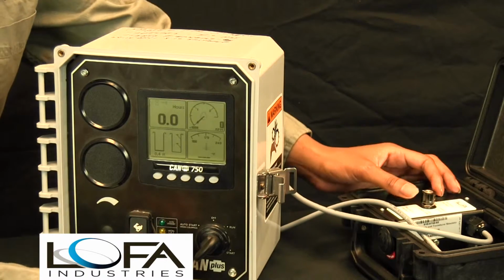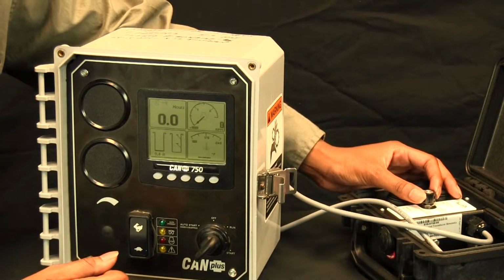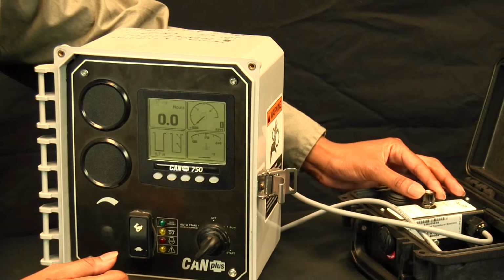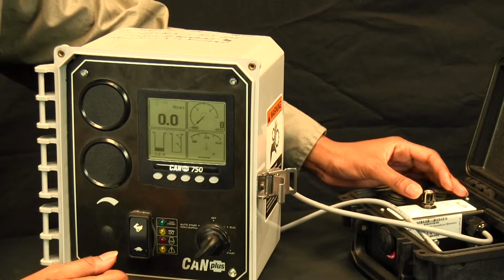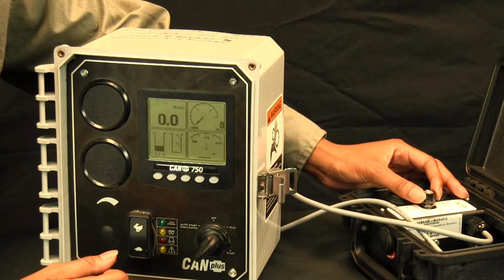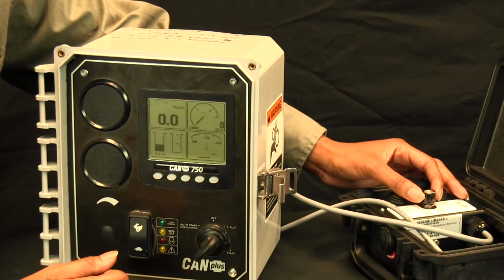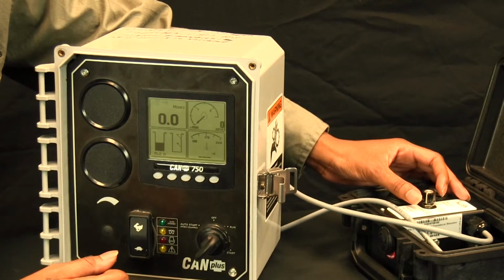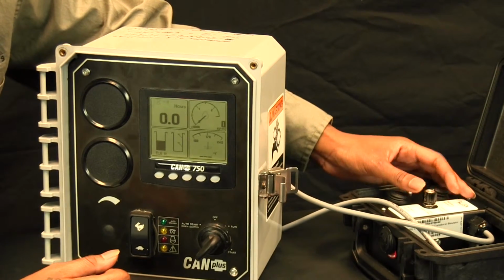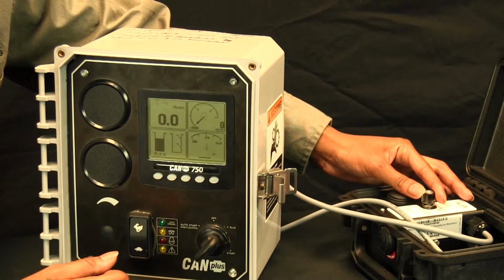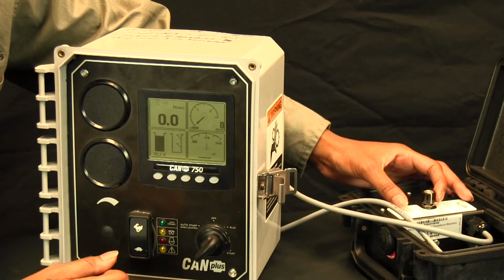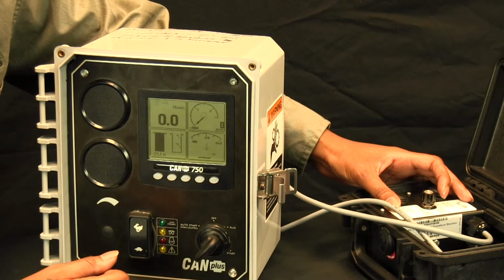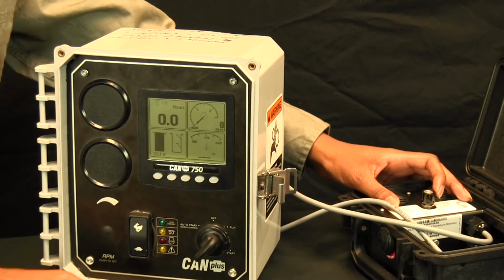Now let's say if you're using a transducer, you see how the container is filling up as I'm using the simulator to send a 4 to 20 milliamp signal into the panel. And depending on what level you have set, that will be the highest that you can reach. The default is 23.1 feet.